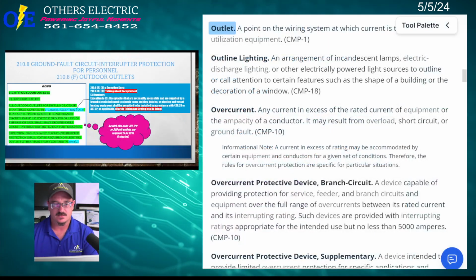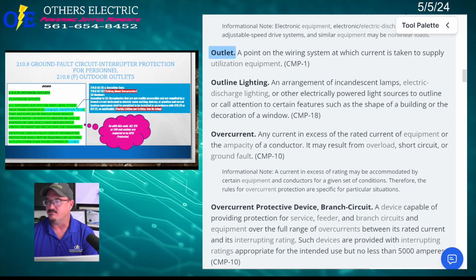Okay, so 210.8F was added to the code. And 210.8F, outdoor outlets. Okay, we're not talking about outdoor receptacles. This is outdoor outlets. What is an outlet? A point in the wiring system at which current is taken to supply utilization equipment. Okay, so if you got a junction, if you got a box with a blank on it that feeds, it doesn't matter what it feeds.